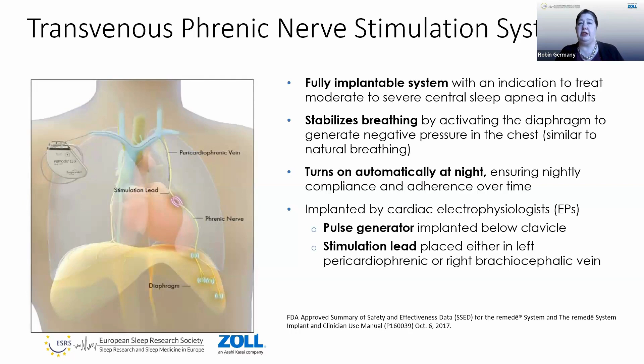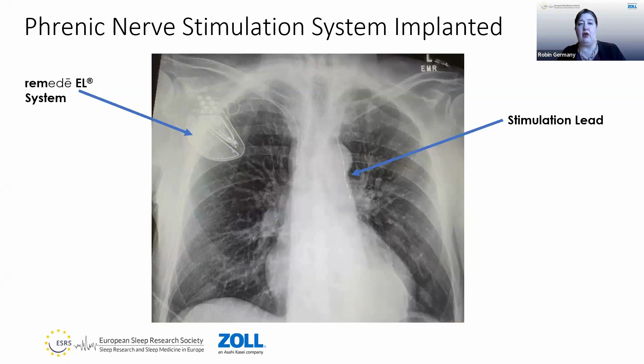And the way that it does that is because it has a position sensor and algorithms in it to help it do that. This is what it looks like on the X-ray. You can see there it has, on the left side, four different electrodes, so you can program different ways to make certain that it's the lowest amount of energy the patient needs to stimulate that diaphragm. But this is what it's going to look like. About 40% of the patients have a pacemaker defibrillator. So it's almost always put in on the right side, because the thought process is if they don't have one, they might need one later. And there are some benefits to putting the cardiac devices over on that left side.